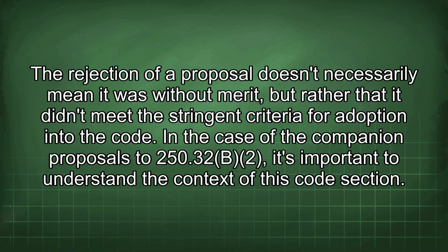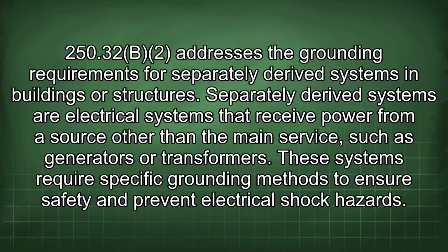In the case of the companion proposals to 250.32 B2, it's important to understand the context of this code section. 250.32 B2 addresses the grounding requirements for separately derived systems in buildings or structures. Separately derived systems are electrical systems that receive power from a source other than the main service, such as generators or transformers. These systems require specific grounding methods to ensure safety and prevent electrical shock hazards.